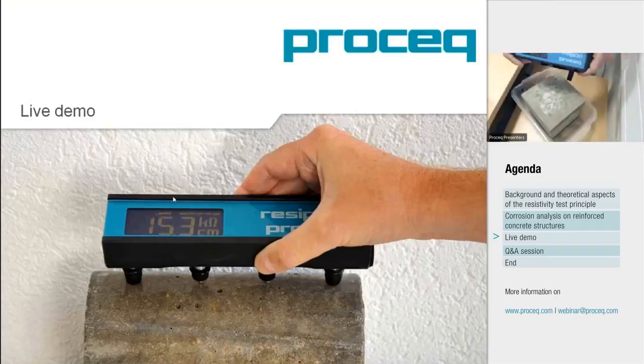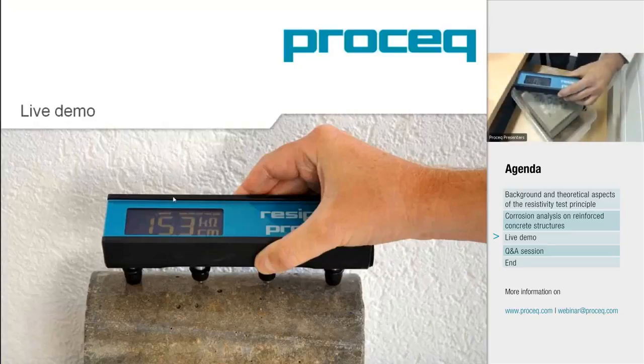Okay. We actually needed a real structure here, which we do not have. So let's be happy with this cube, which we might assume to be a bridge deck or whatever. It was just a chance to take a closer look at our instrument. Especially on site, the use of spring-loaded probes allows us to adapt the measurement even to irregular surfaces. The idea, of course, is just to have a proper contact to the surface. And here's the reading we get.